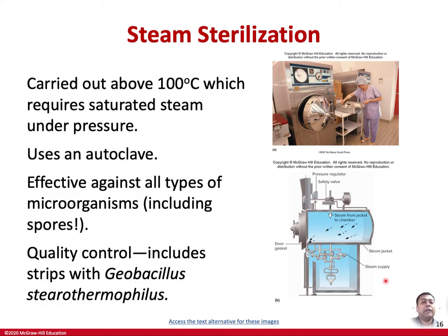There are some autoclave tapes, and they have some white marks on them, and you can put them onto the material that you are sterilizing. After they come out, you will see those white stripes have turned into black stripes. So those are heat sensitive stripes. What we mean by that is if the temperature of the chamber reaches 121 degrees Celsius, then those white stripes will turn into black stripes. But still, there could be some problems with that. It is not the best process.